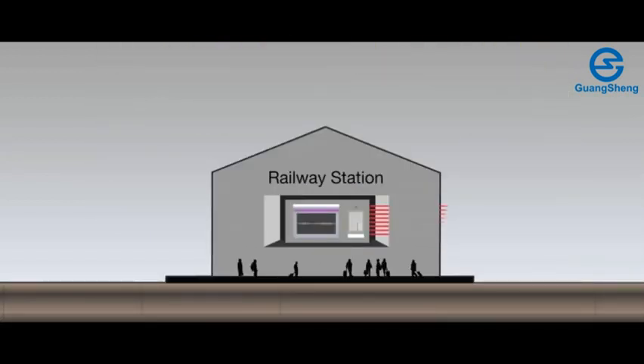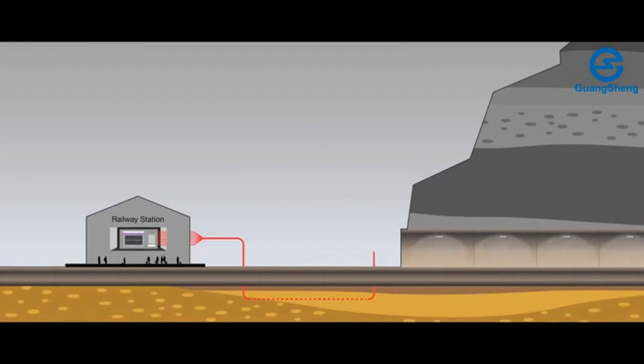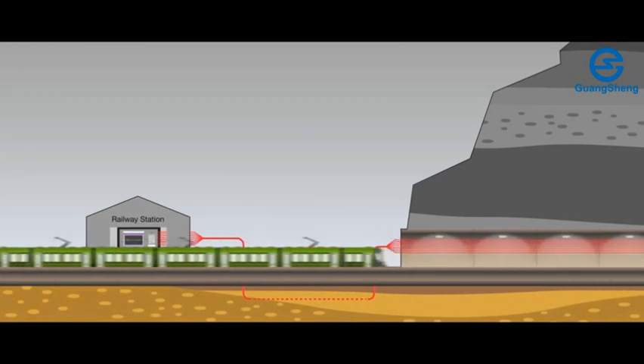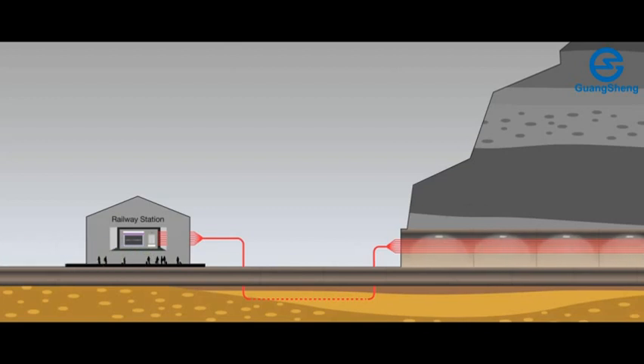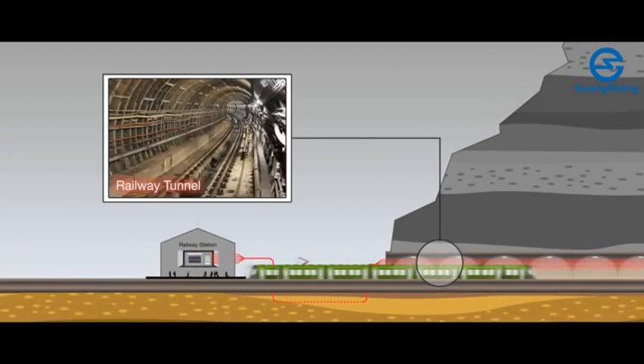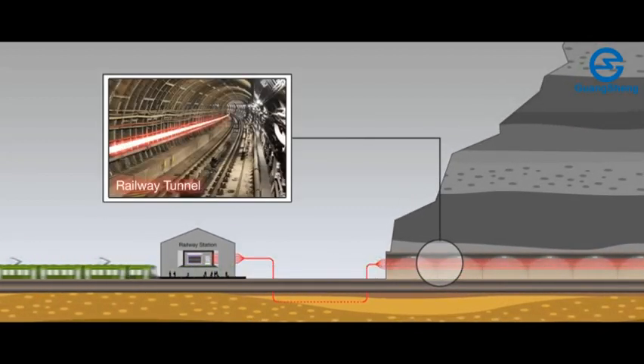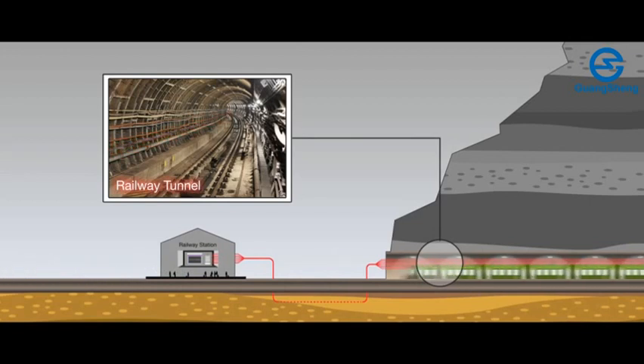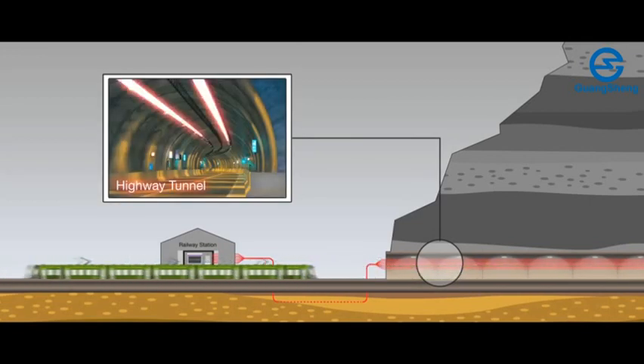It is possible to know in real time all the temperatures meter by meter and to receive alarms in case of hotspots anywhere along the tunnel. Moreover, we always know the location of the hotspot. For this reason, DTS solutions are used for medium-long tunnels because we need to know the location of the heat source in a very accurate way.